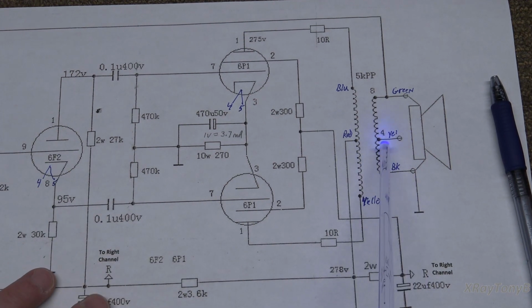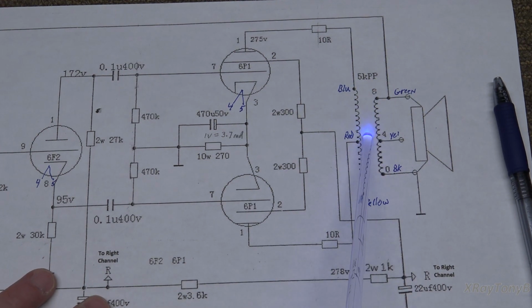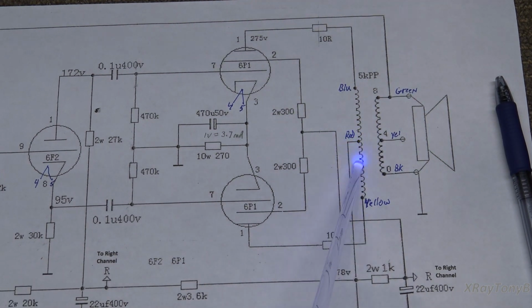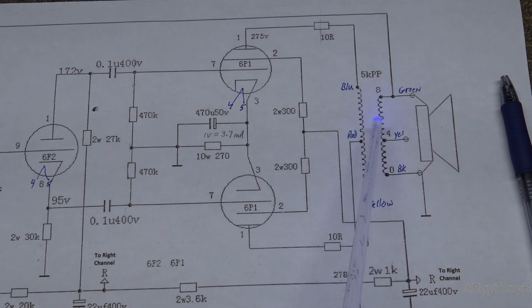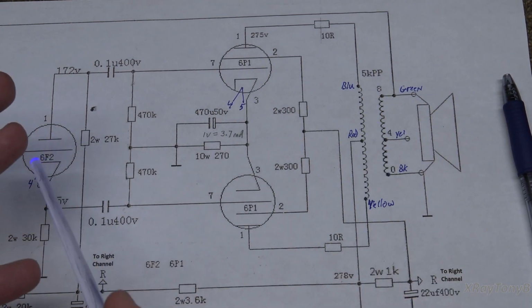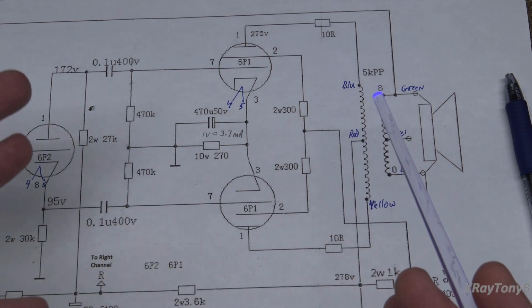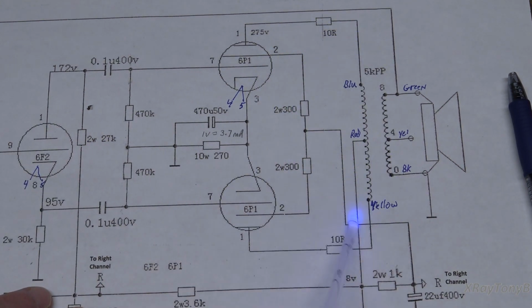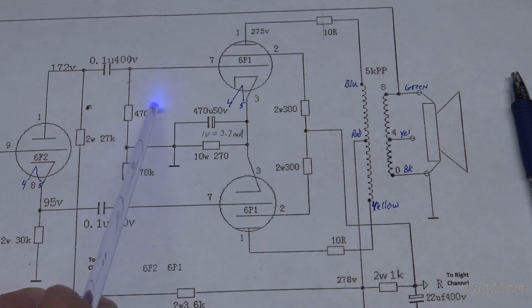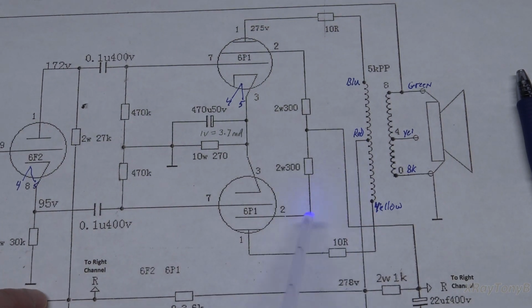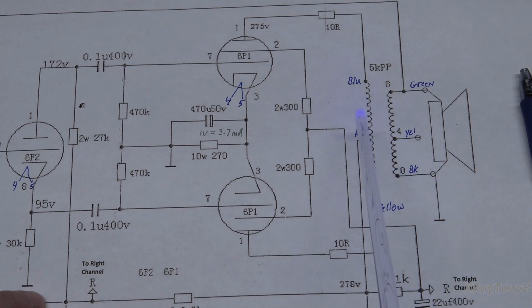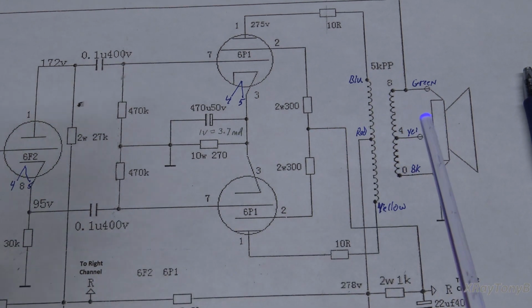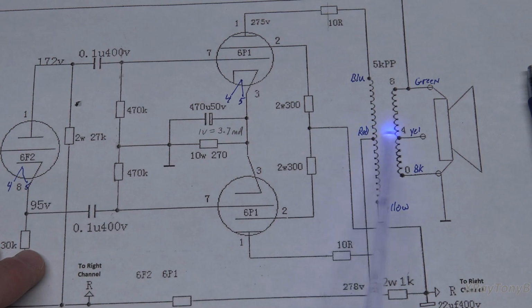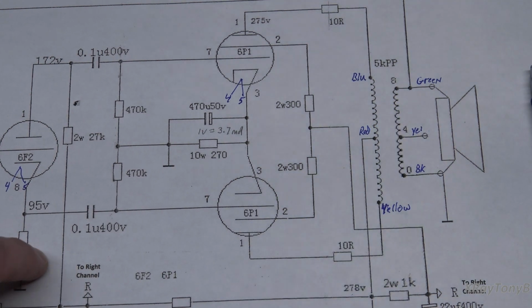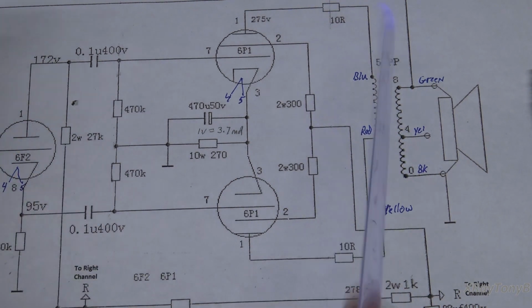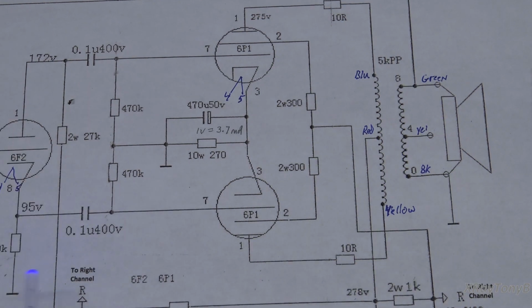But anyway, this will cause the current to flow in one direction. It magnetizes the core, and the core will no longer be magnetically neutral when you take the voltage away -- it'll turn into a magnet itself. And when current has to flow the opposite direction, or the magnetic field has to collapse, that magnetized field will oppose it, which can cause problems. So they put that air gap in the core so it can't saturate or magnetize and get that core memory.